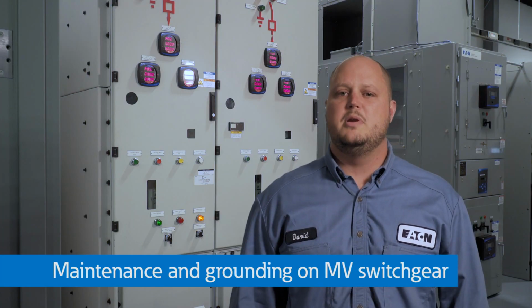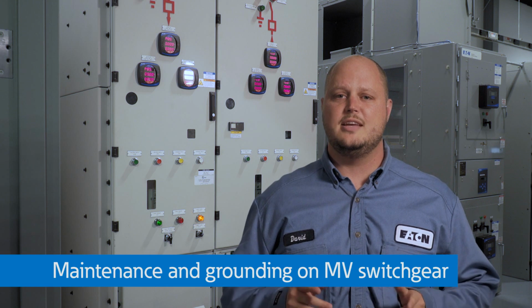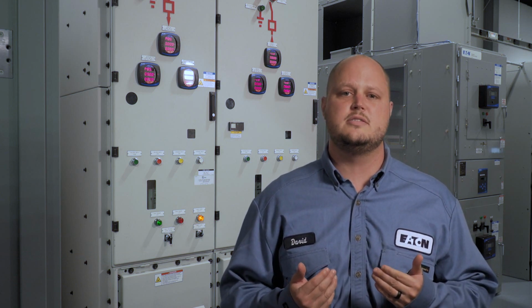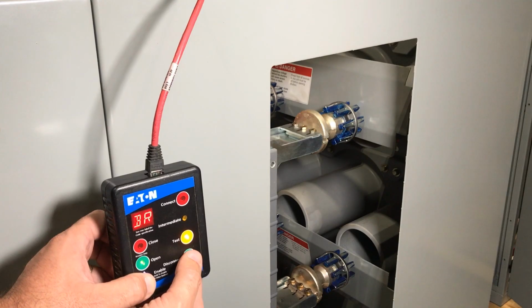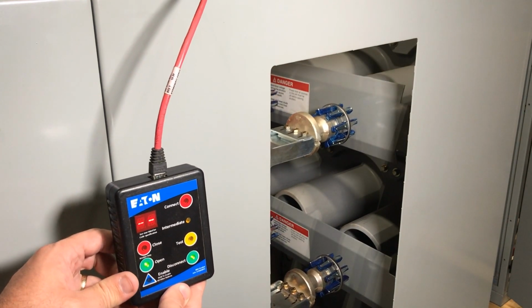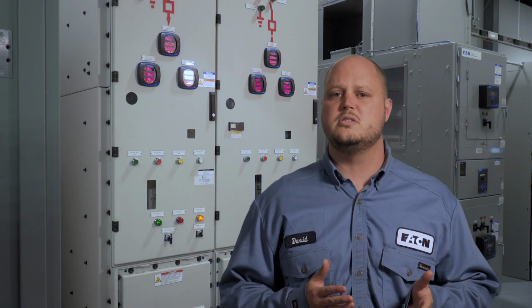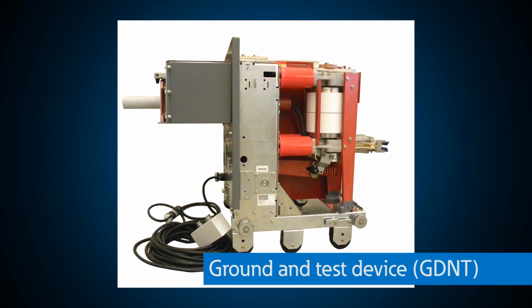When performing maintenance on medium voltage switchgear, it is critical to isolate and ground medium voltage circuits. For ANSI or IEEE metal-clad and metal-enclosed switchgear with withdrawable or draw-out circuit breakers, the circuit is isolated by opening the vacuum circuit breaker and then withdrawing the breaker to a disconnected position. Grounding of the circuit is then accomplished through the use of both manual and/or electrical ground and test devices such as this ground and test device.